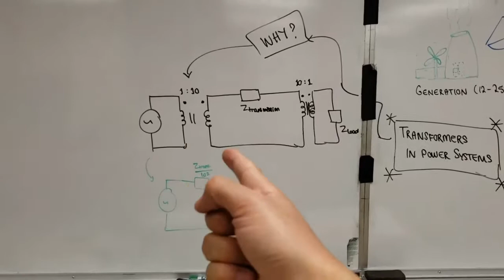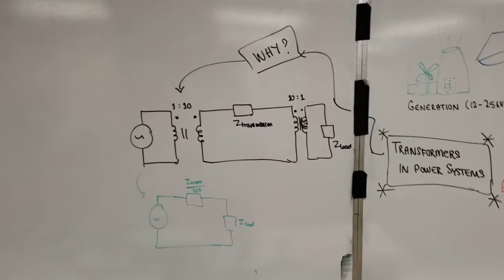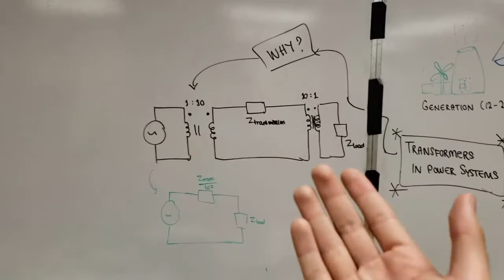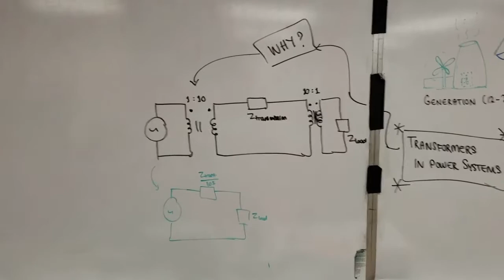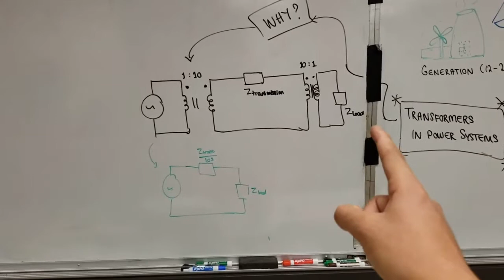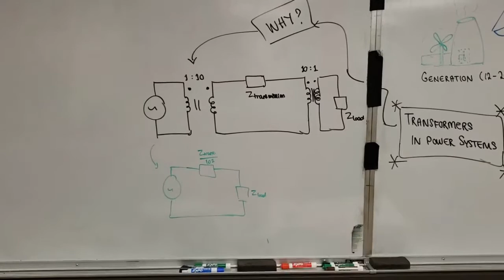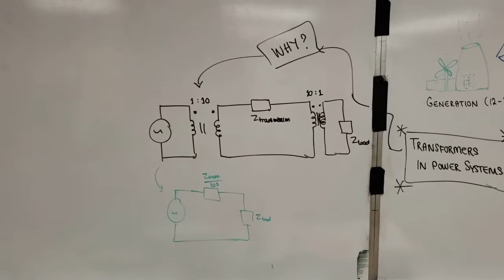Your load needs to operate at a certain voltage level. Because the transmission line is there, due to basic voltage division, power generation needs to occur at a higher voltage in order to get the required voltage specification at the load side. So we have a problem: the transmission line takes away some power from the load, and it also pushes those requirements back, not to the customer—obviously you're not going to change your requirements, so the utility company has to produce more power and operate at a higher voltage.